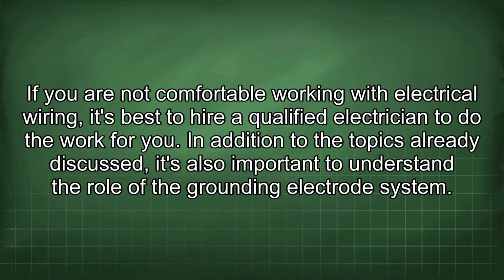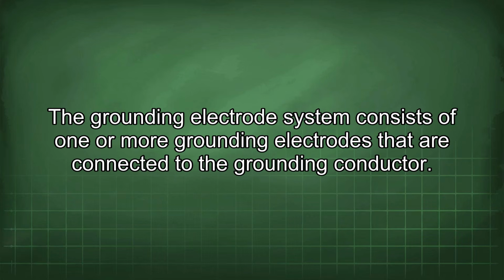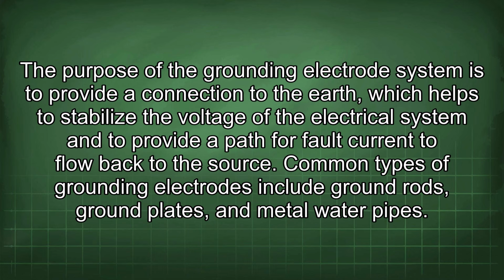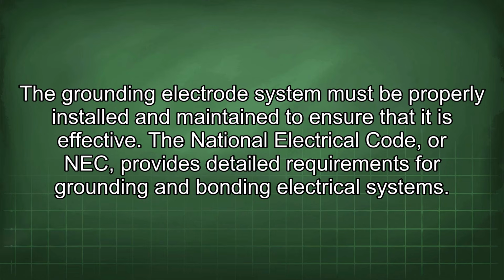for you. In addition to the topics already discussed, it's also important to understand the role of the grounding electrode system. The grounding electrode system consists of one or more grounding electrodes that are connected to the grounding conductor. The purpose of the grounding electrode system is to provide a connection to the earth, which helps to stabilize the voltage of the electrical system and to provide a path for fault current to flow back to the source. Common types of grounding electrodes include ground rods, ground plates, and metal water pipes. The grounding electrode system must be properly installed and maintained to ensure that it is effective.